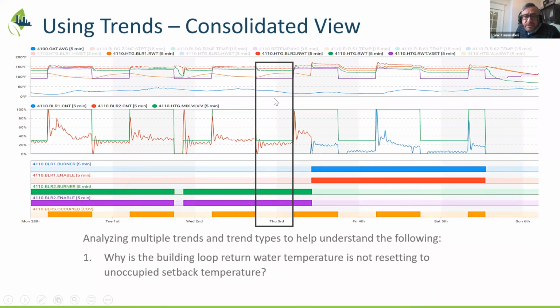If you remember in the first slide, we were having a problem with the valve. The set points were being set back, this purple line, but the actual temperature in the loop wasn't going back. By having all of this information in one place, which is becoming more common in fault detection and diagnostic tools and with some BAS manufacturers, we're trying to understand why that's happening.